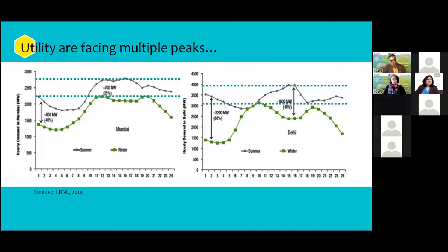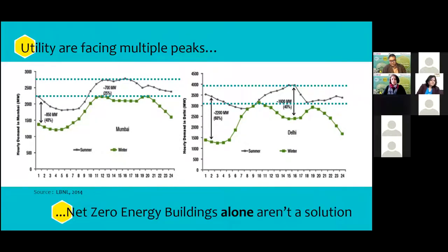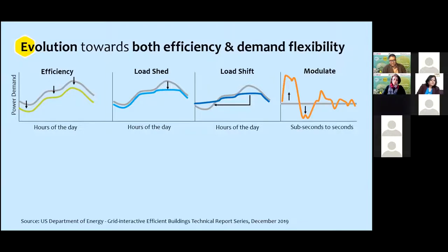In this light, if we look at scaling net zero energy buildings, which have an inward looking approach governed by self-consumption, it is not really an integrated solution. These buildings need to evolve, addressing both high performance in terms of energy efficiency and providing demand flexibility that enables us to flatten the load curve. So first and foremost, it comes down to efficiency. Then we move on to load shedding, where we can drop off certain load where we don't need it, or shift certain loads to the times that it is required. I mean, it can be moved from midday to morning, things of that sort. And lastly, load modulation, which looks at the ability to provide voltage stability and contributes to improved power quality.